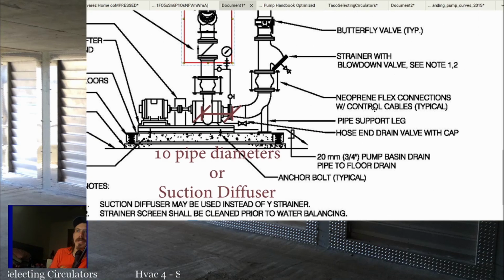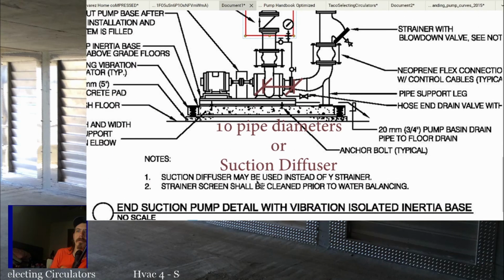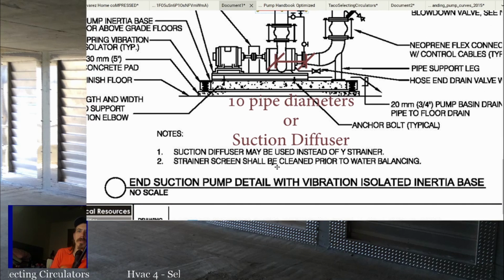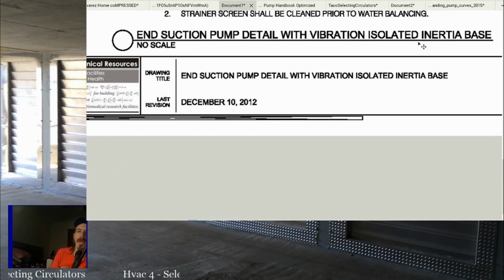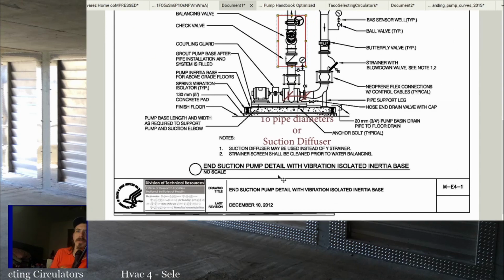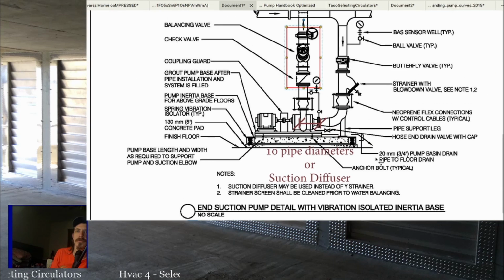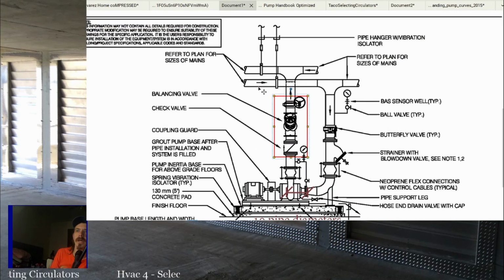So those are the parts. And notice here, suction diffuser may be used instead of a Y strainer, and it replaces that 10 pipe diameters. And the strainer screen has to be cleaned prior to balancing the system. It's just their notes. This is just some typical detail I found online. But these are the parts that you will have associated with your pump a lot of the time.